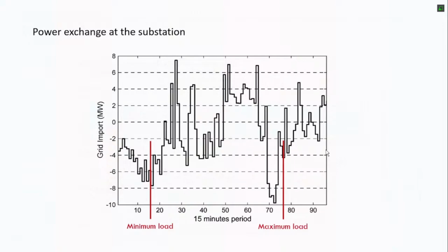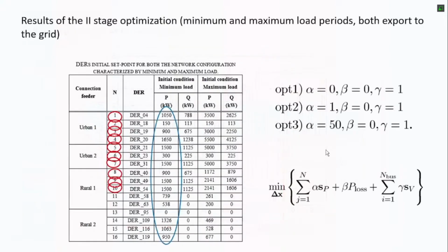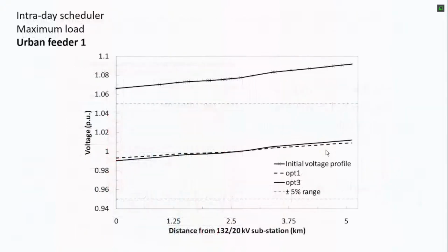Both are periods in which the power at the substation is negative, so the power flows from the distribution network to the transmission network. These are the values at the 2 points, minimum load and maximum load, and these are the voltages along the feeder for the maximum load. You see that for the day-ahead scheduling, the voltage was very high, and then it decreases, and there are also 2 bands.